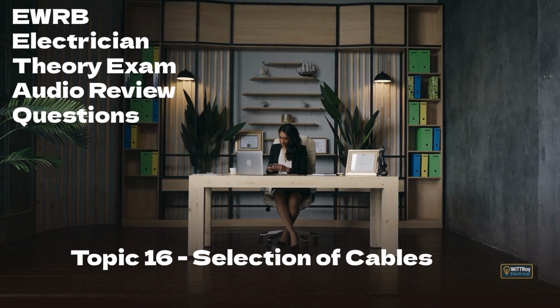Pause. 5, 4, 3, 2, 1, 0. Correct answer is option A. Different devices trip differently at the same fault current. You must ensure the expected fault current will make the device trip within the required time so touch voltage and heating are controlled.